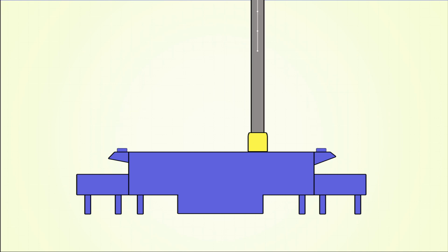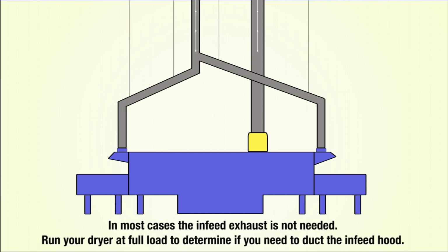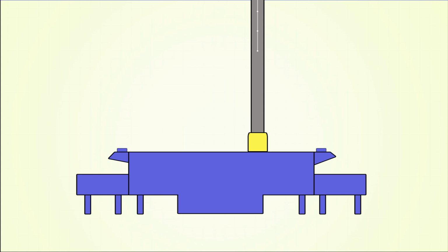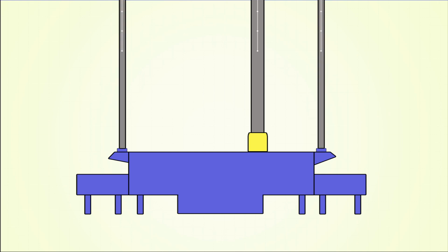Some M&R customers choose to run additional exhaust ductwork from the infeed and outfeed hoods on M&R gas dryers. This ducting is connected to each 6-inch flange. The duct is then run at a 45-degree angle above the dryer, then connected into a single and separate duct, which is vented through the ceiling. Another way of running exhaust ductwork from the infeed and outfeed hoods is by connecting individual stacks to the 6-inch flanges, then venting them straight up through the ceiling.